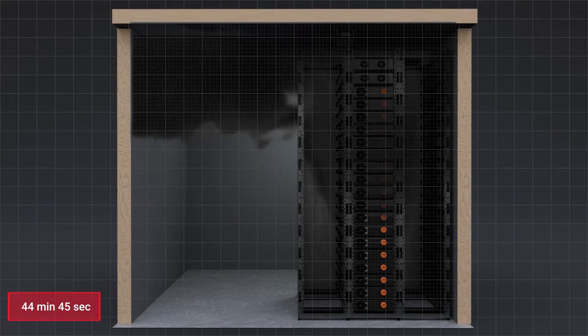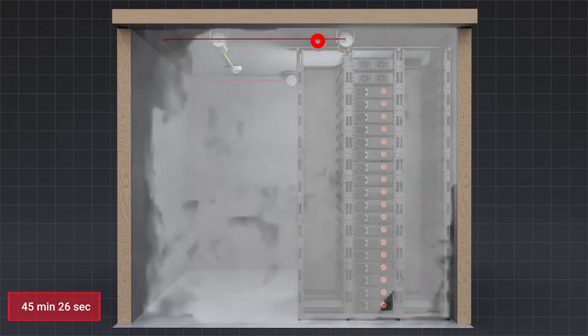At 44 minutes and 45 seconds, heavy smoke was building within the enclosure and the second smoke alarm was activated. At 45 minutes and 26 seconds, the Stat-X system was activated and the aerosol was released for 30 seconds, inhibiting propagation of thermal runaway to adjacent battery racks.